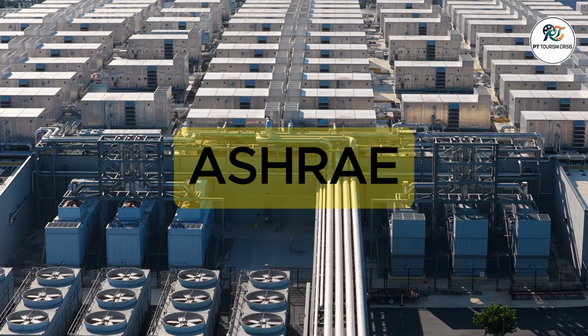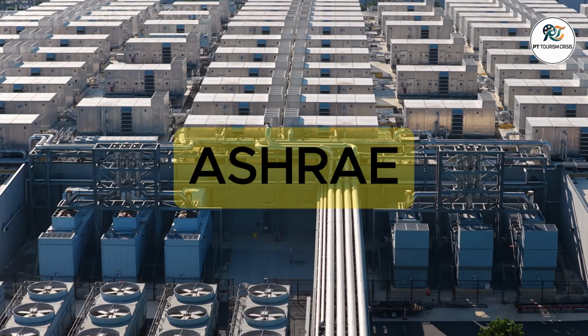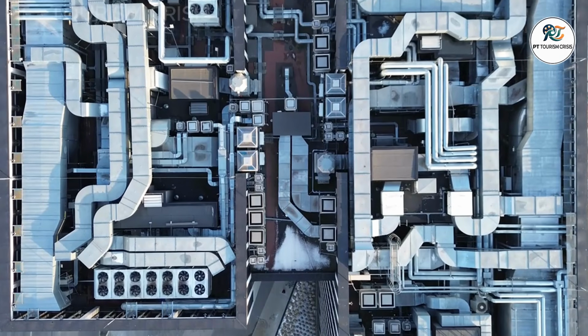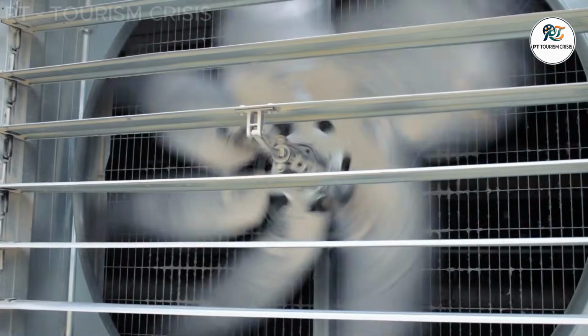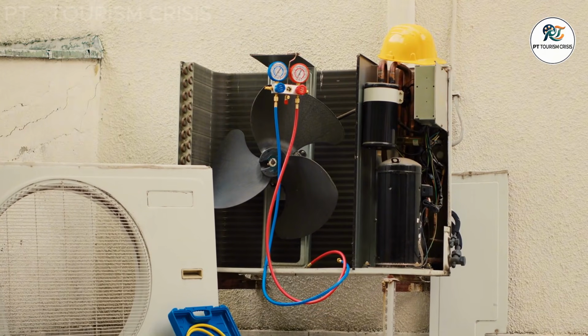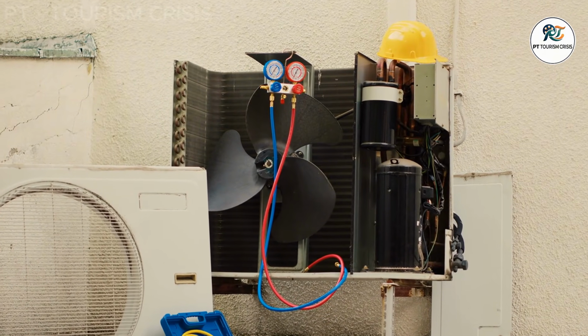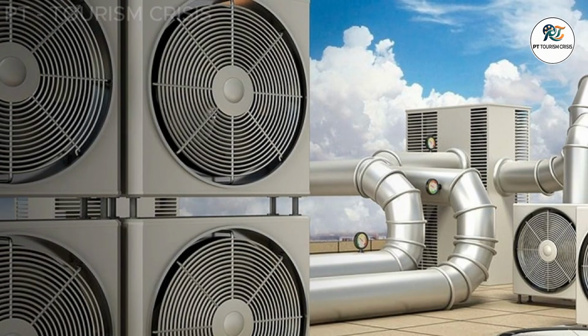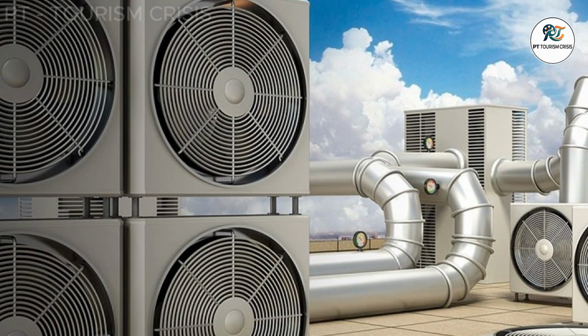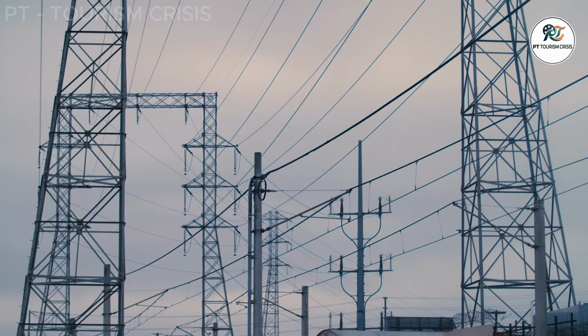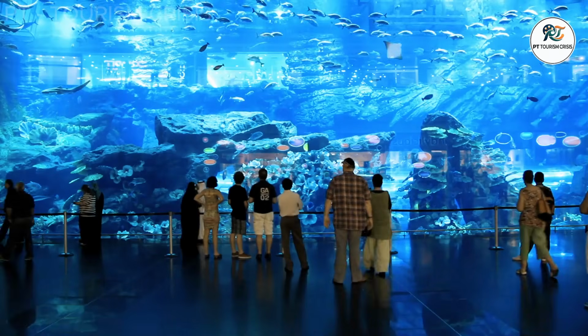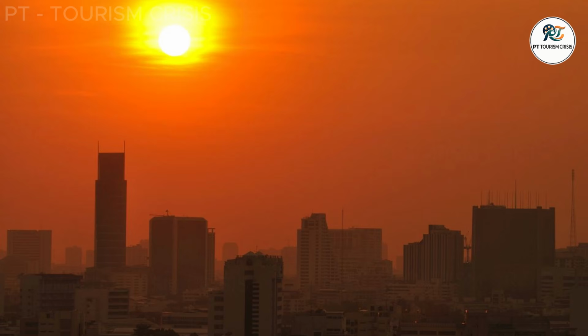ASHRAE's traditional benchmark exposes the hidden arithmetic. A system removing 12,000 BTU per hour as one refrigeration ton may need to reject about 15,000 after compressor work is added, although modern equipment can narrow that gap. So every protected bubble has another side: a condenser, a cooling tower, an electrical demand, and a place where the heat is released. The customer buys the cold. The outside world receives the thermal invoice.